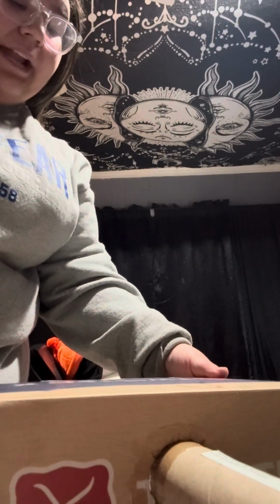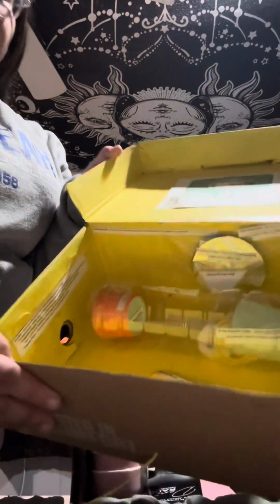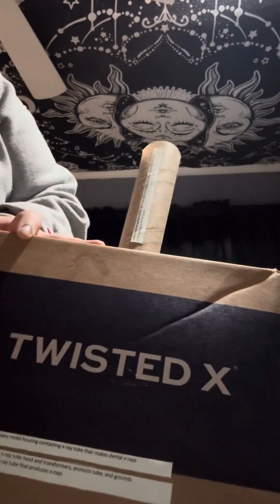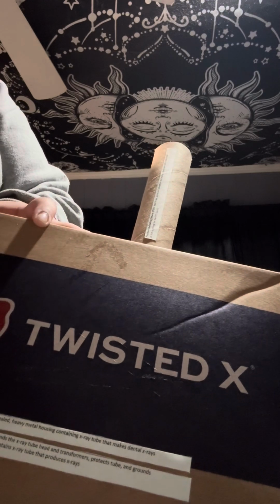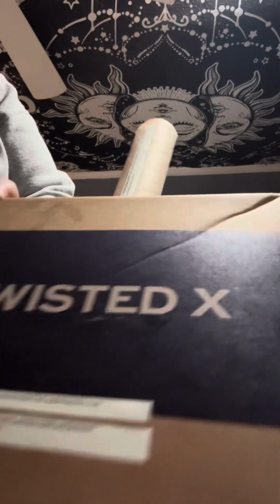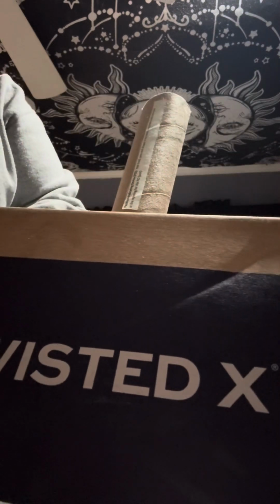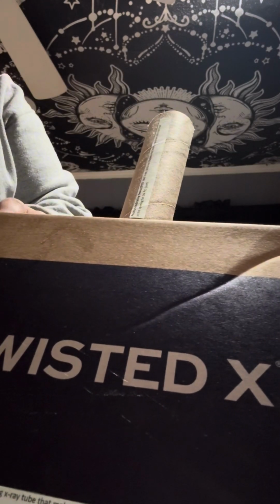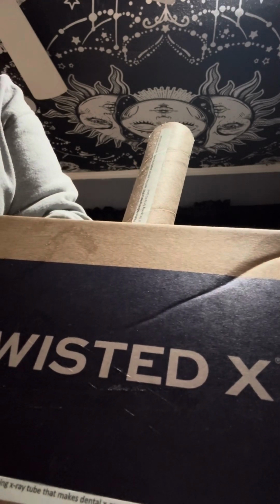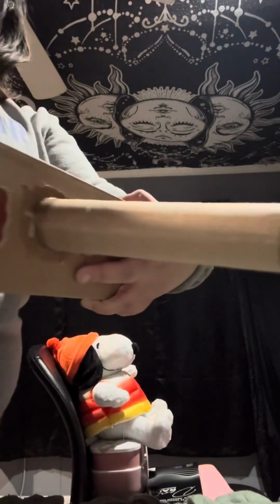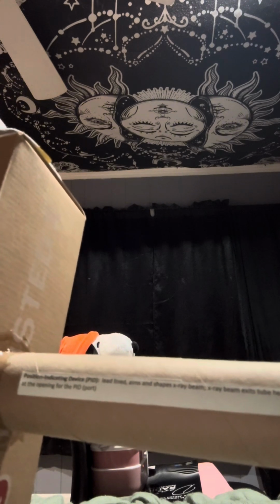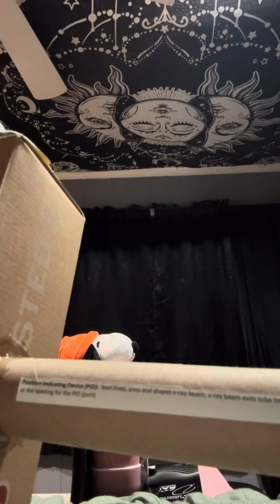So now inside our dental tube head, we can open it up, and this is what it would look like. The tube head, this whole device right here, is a tightly sealed heavy metal housing containing the x-ray tube that makes the dental x-rays. What surrounds it is the metal housing that contains an x-ray vacuum tube and transformers, and protects the tube and the high voltage components. And then on the outside, like I was stating earlier, is our PID, also known as our position indicating device. It is lead lined, and it aims and shapes the x-ray beams, and the x-ray beams exit out of the tube head at the port right here.